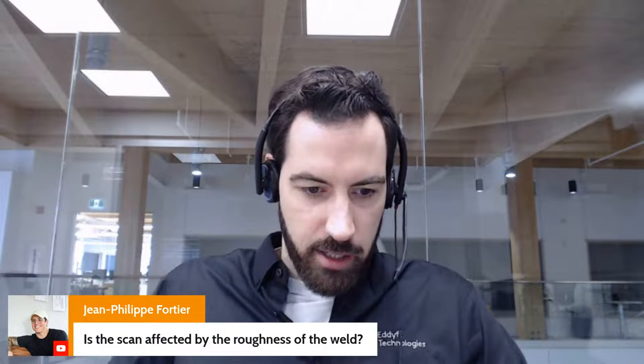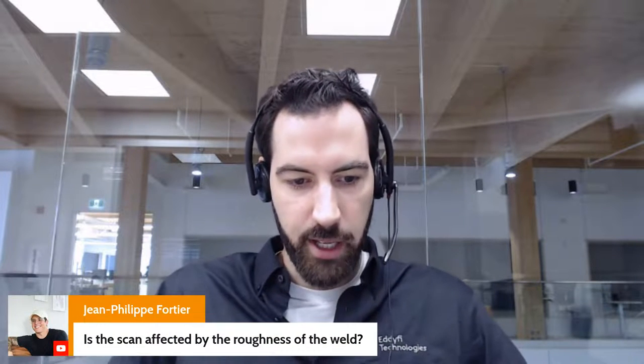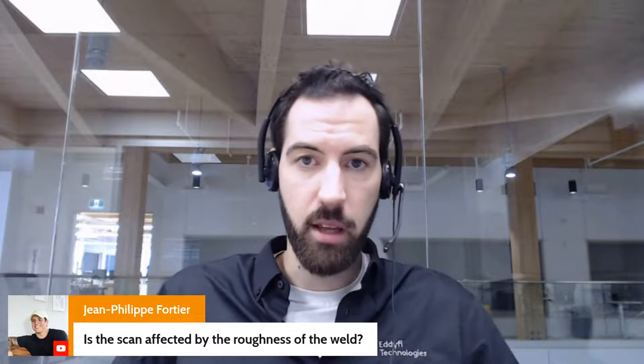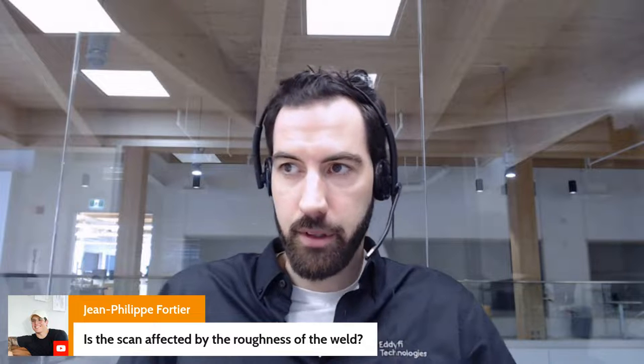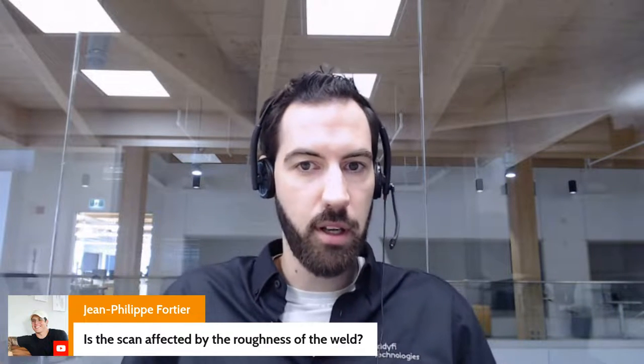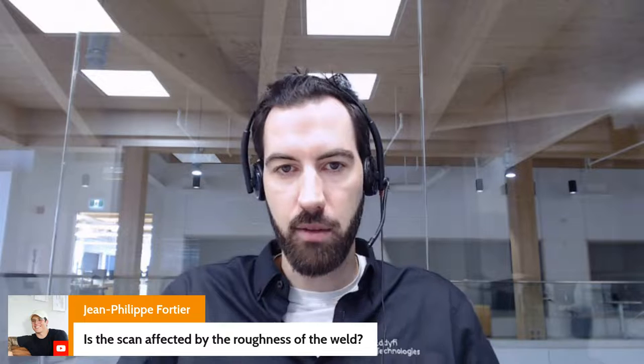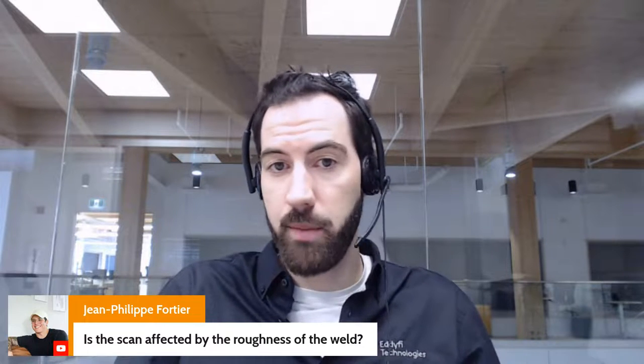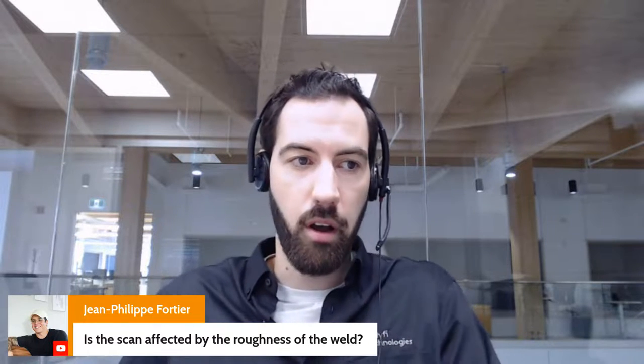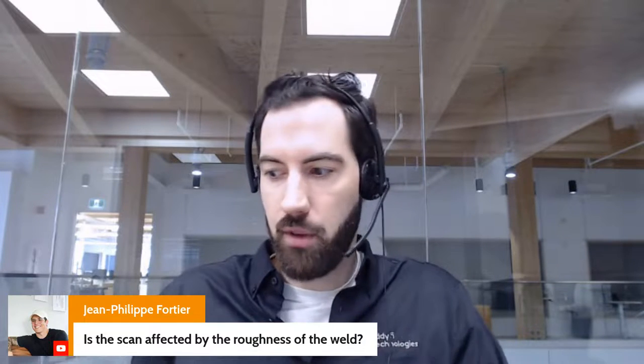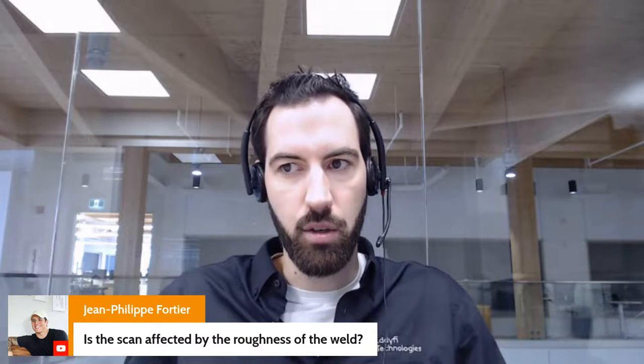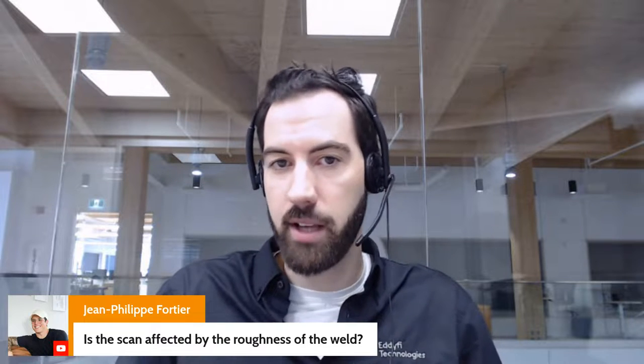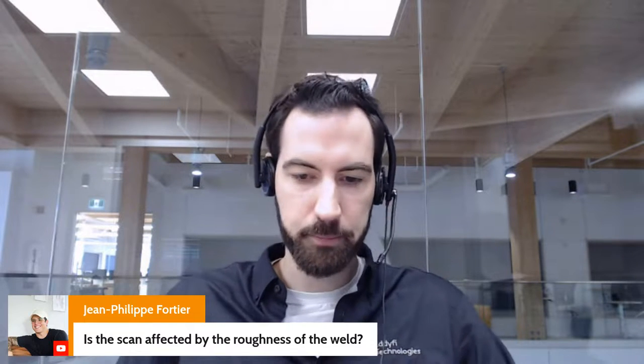Is the scan affected by the roughness of the weld? Yes, it is. As I explained, you will see more noise and more indications of roughness. But using that differential C-scan with the blue and red combination, you will never mistake a crack for roughness or geometrical features. So even though it will affect the data, the crack detection and crack sizing will not be affected by it.